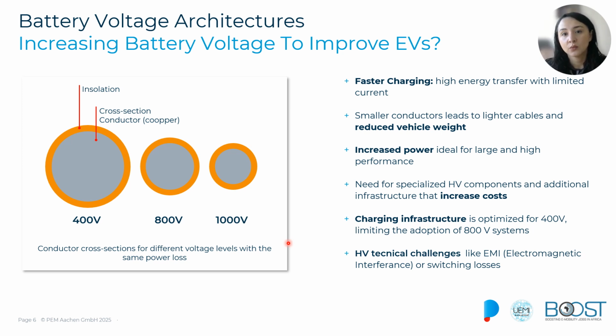It also means we will have smaller conductors, with significantly reduced physical dimensions. In a 400 volt system, for instance, the current is higher for a given power output, requiring thicker cables to prevent overheating and excessive power loss. In an 800 volt system, the current is halved for the same power, meaning we need thinner cables without increasing power loss.